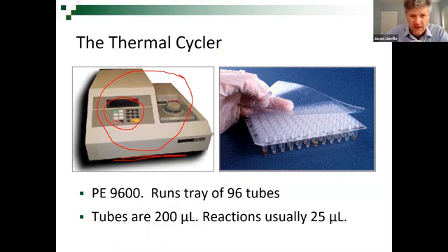But this knob, you unscrew, and this whole tray slides back. And then you put your individual samples, which sometimes in larger labs that run high throughput, a lot of samples at one time, there'll be this tray where you can see these are just a whole bunch of tiny little tubes. And this whole tray goes in the instrument right there.